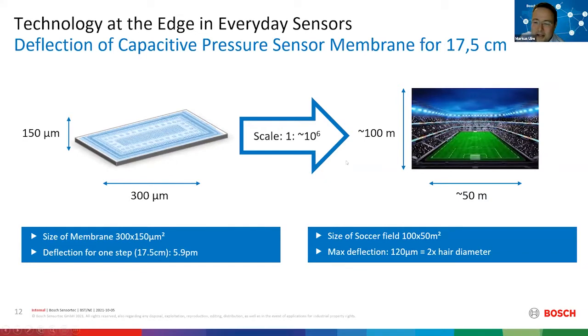In the following, I like to do soccer examples for whatever reason. If you compare this capacitive pressure sensor membrane with a soccer field, it roughly has a scaling factor of 1 million, not exactly. That would mean the deflection of 5.9 picometers of this membrane needed to resolve a step equals a change in deflection of a soccer field by 2 hair diameters. So really a nice piece of technology to get this done, and for me very fulfilling to work on things like this.